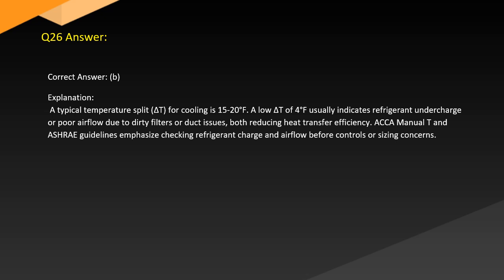Answer. Correct answer: B. Explanation. A typical temperature split, or delta T, for cooling is 15 to 20 degrees. A low delta T of 4 degrees usually indicates refrigerant undercharge or poor airflow due to dirty filters or duct issues, both reducing heat transfer efficiency. ACCA manuals and ASHRAE guidelines emphasize checking refrigerant charge and airflow before controls or sizing concerns.